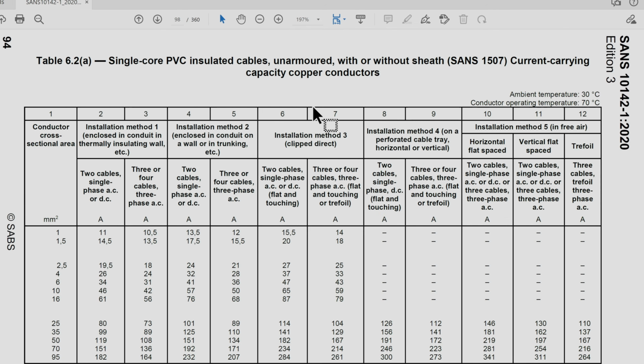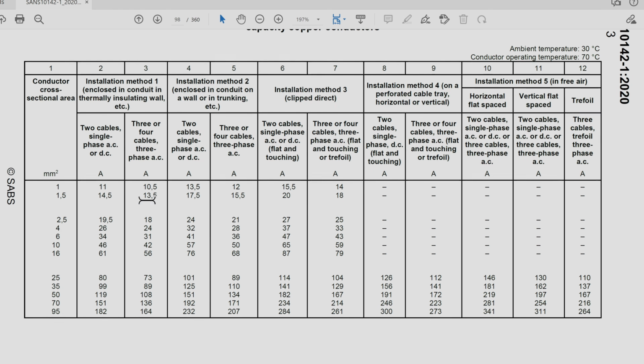Now I'm going to specify the cable size from this table over here, which I got from the SANS 10142 standard, and this specifies cables for AC or DC applications, and this will be single core PVC insulated cables, unarmored, and they specify it according to how the cables are run. They've got installation method 1, 2, 3, 4, and 5 because the current carrying capacity of cable depends very much on how or where the cable has been run.